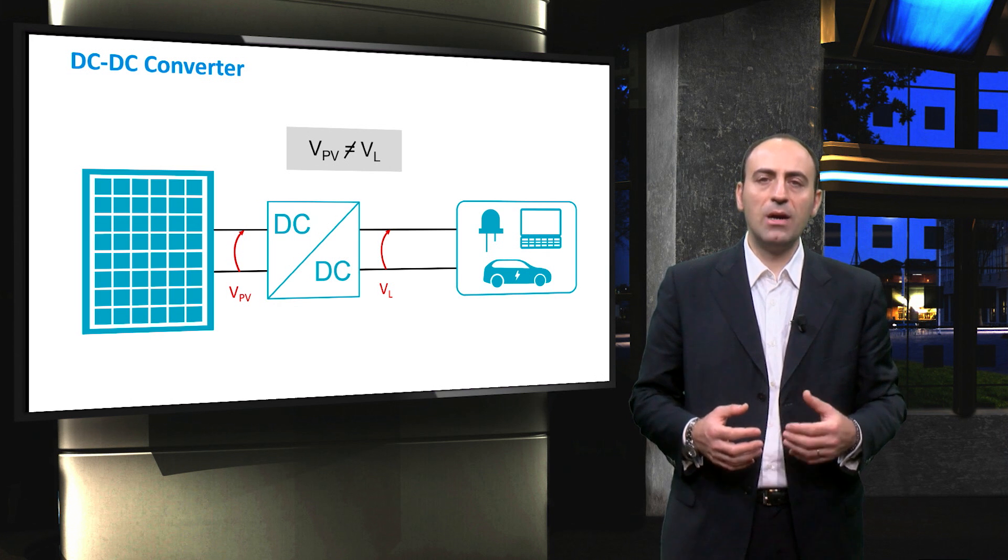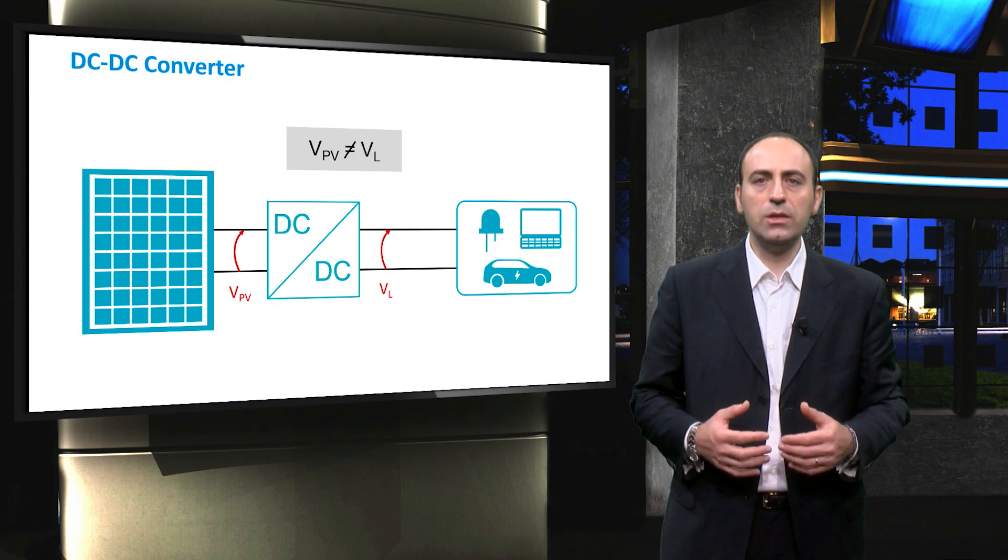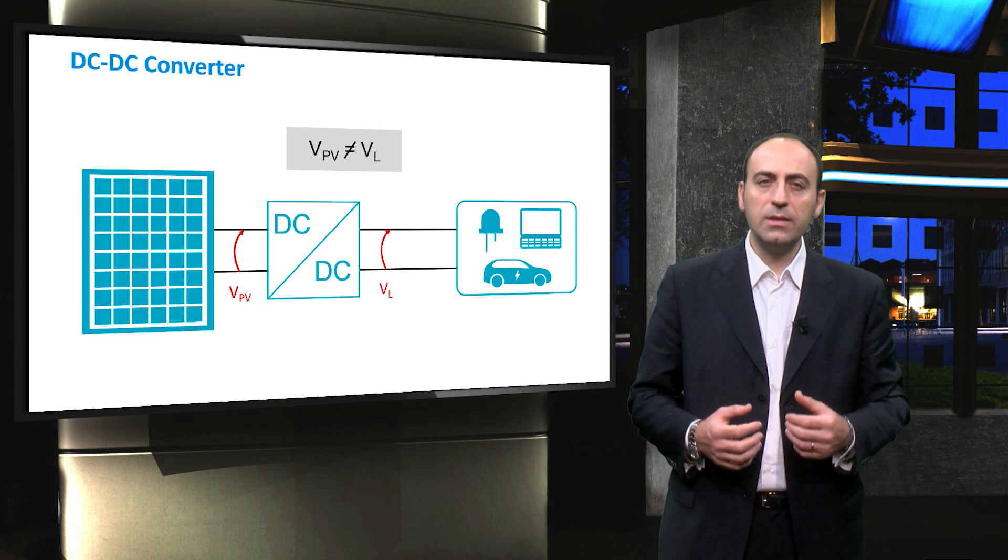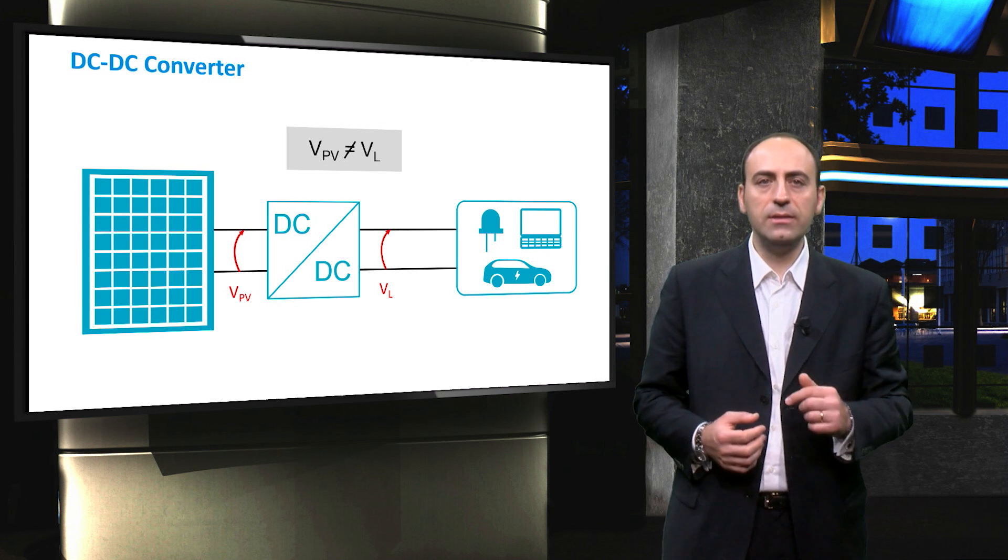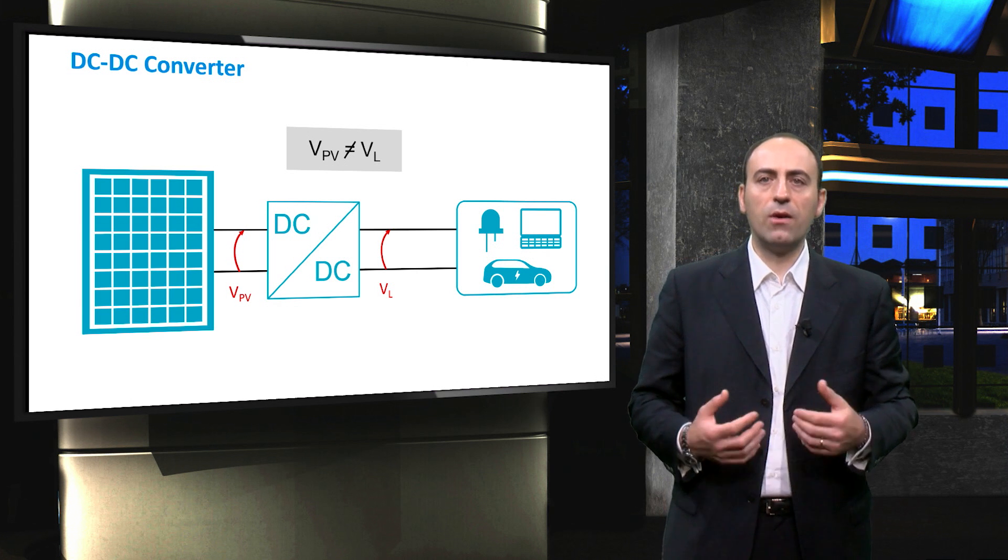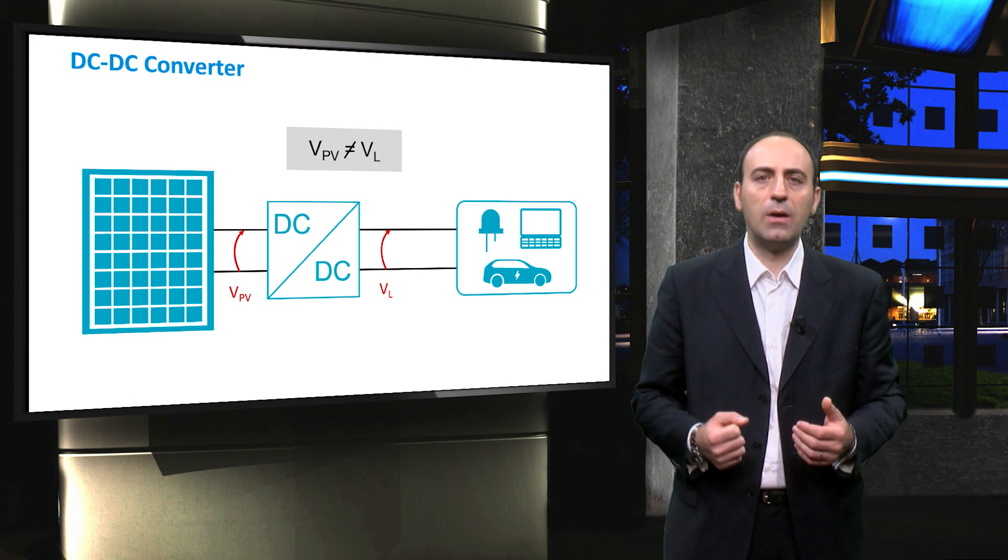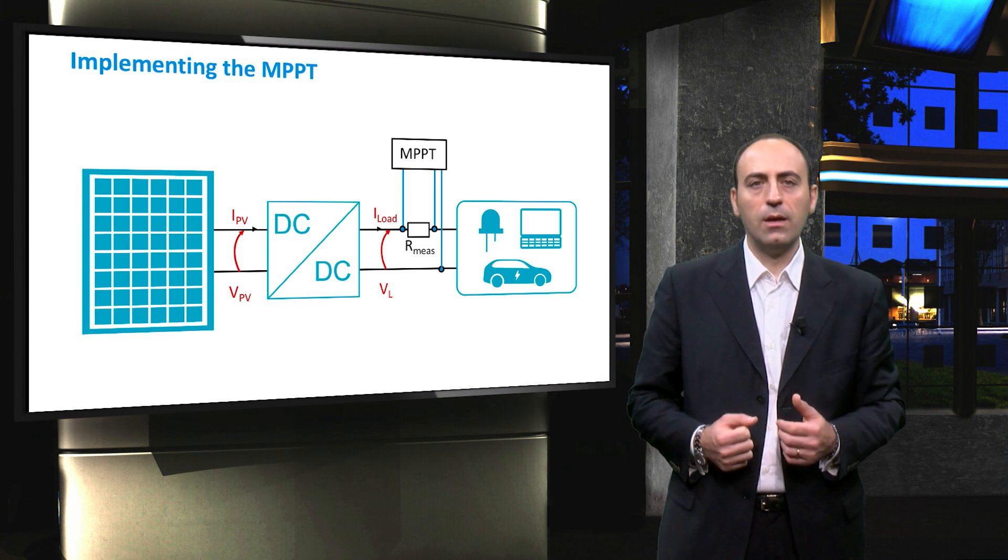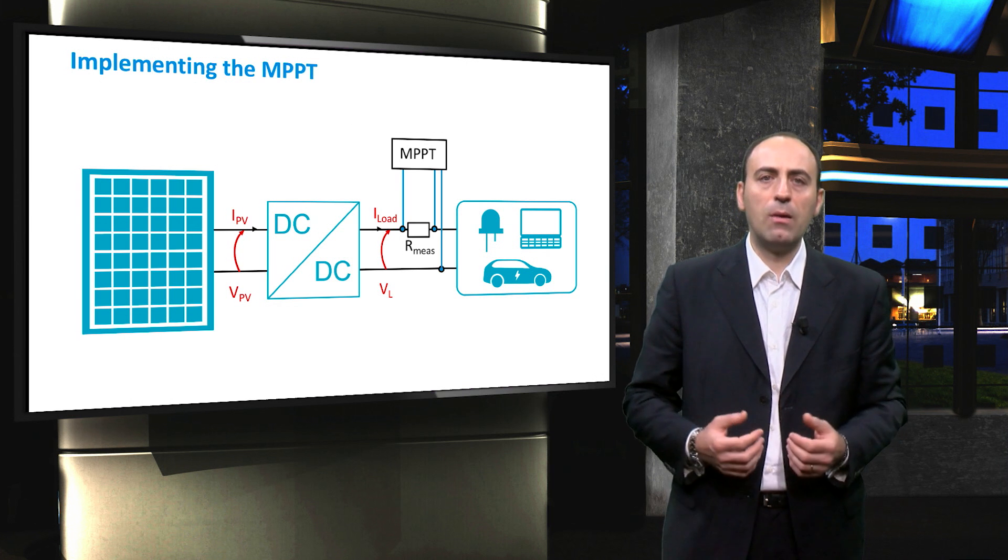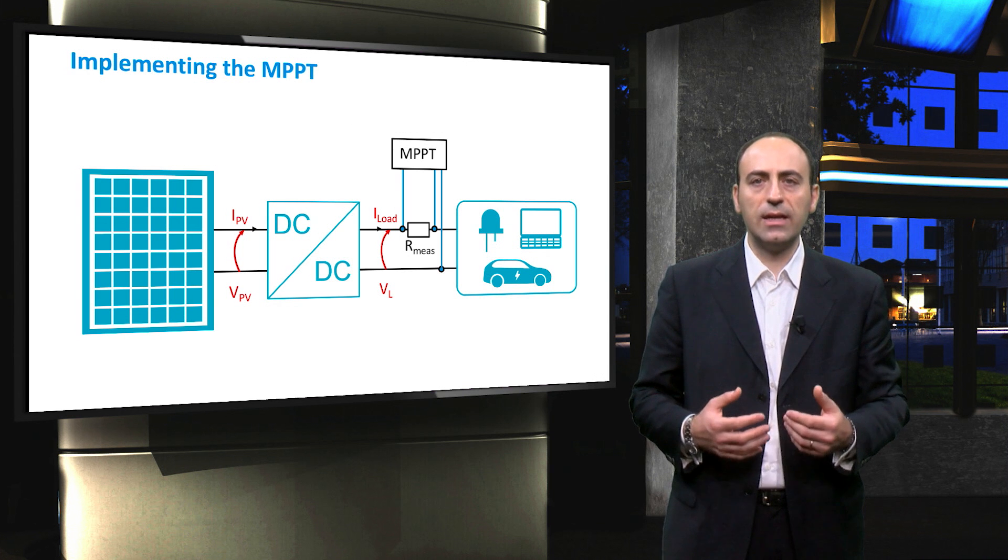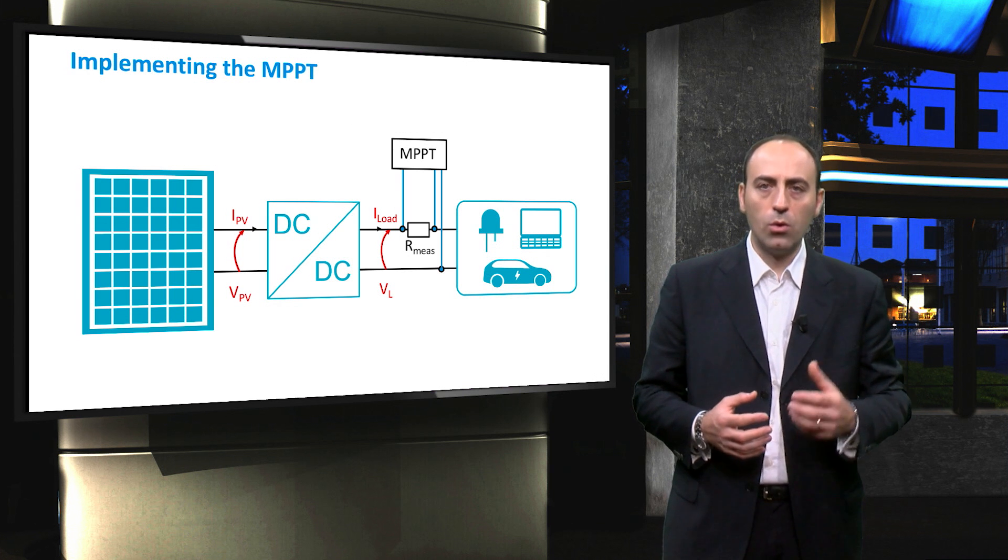We have already seen that the maximum power point tracker controls the operating point of the modules, but cannot set it. This task is then performed by the DC-DC converter, which varies the PV voltage in order to draw always the maximum power available. Adding the maximum power point tracker is nothing else than adding an additional circuit that can be also embedded on the board of the converter.